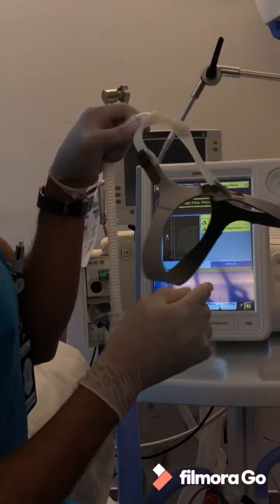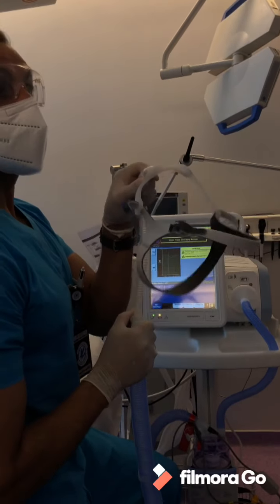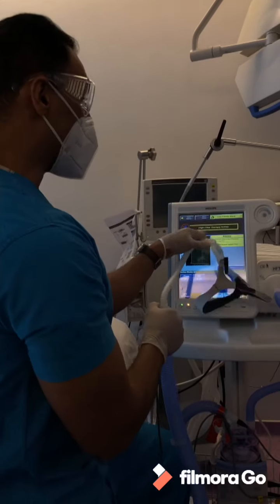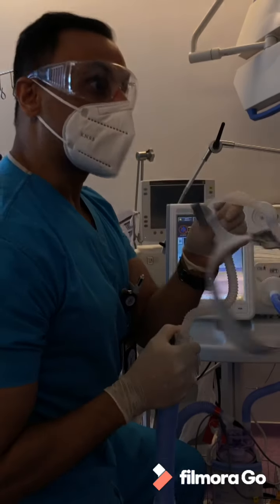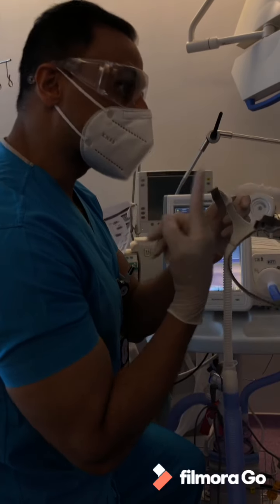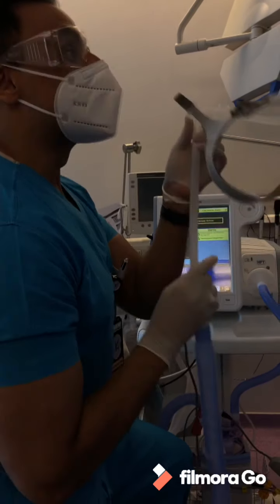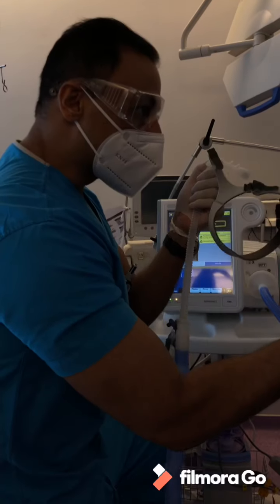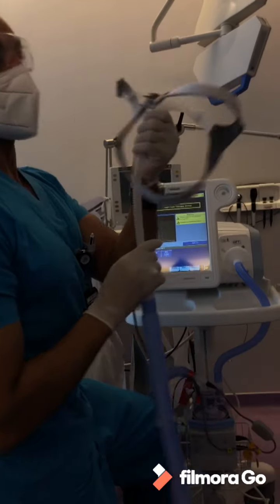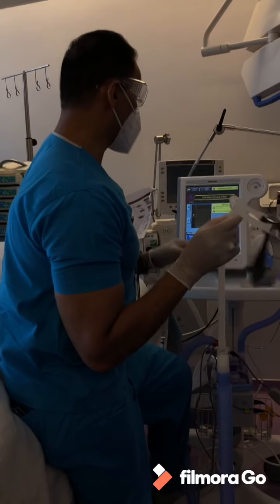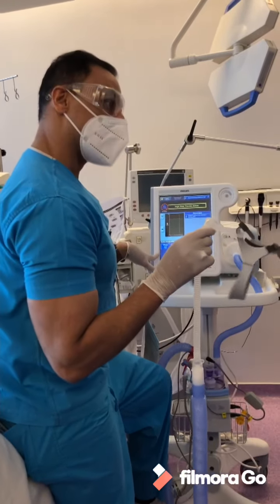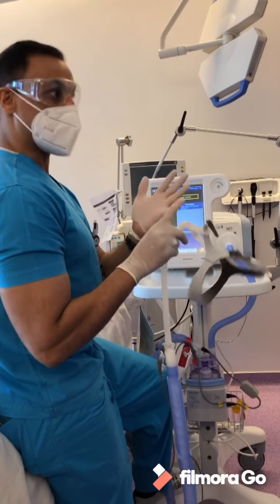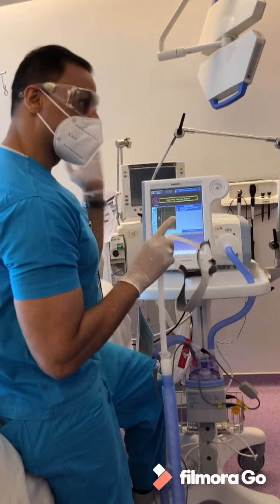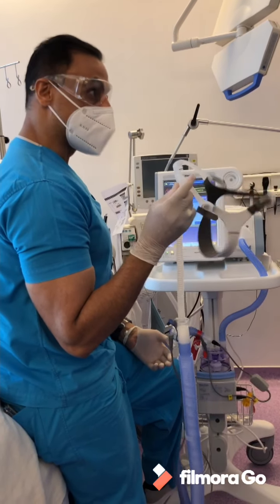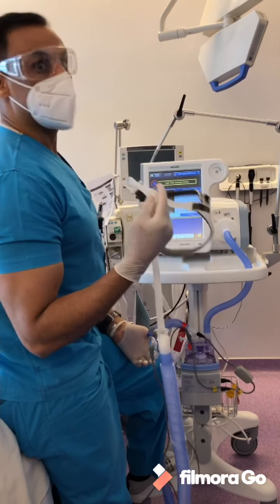It will give this kind of sound, see, that reminds you of what mode in the BiPAP? CPAP. So it gives you only one kind of pressure, continuous positive airway pressure, but this gives you only flow, okay. So you hear this sound, you don't hear inspiratory, expiratory, inspiratory, expiratory. It's only one sound, okay. That means you're giving only flow. So you start with high flow and then you go down, according to the ABGs, according to the patient's vitals.